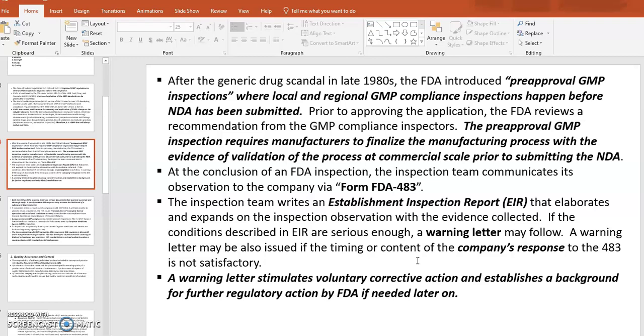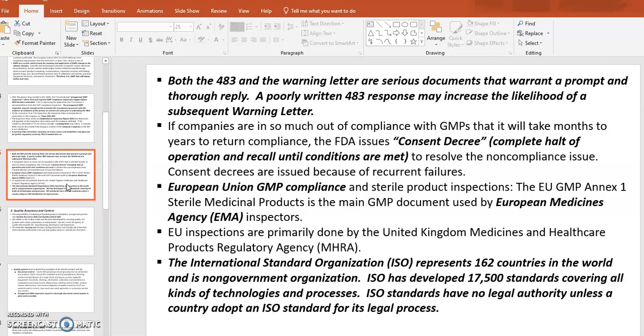A warning letter stimulates voluntary corrective action and establishes a background for further regulatory action by the FDA if needed. Both Form 483 and the warning letter are serious documents that warrant a prompt and thorough reply. Companies typically have a short window — about two weeks — to respond. If the response is poorly written, it may trigger a subsequent warning letter.